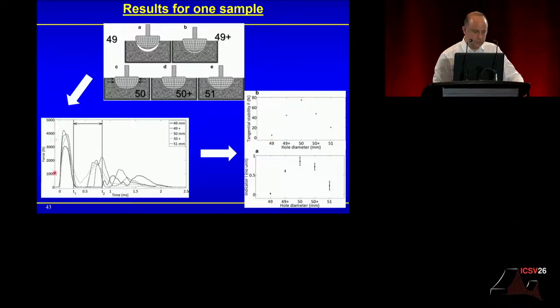Very simple, nothing related to acoustics. But what is related to acoustics is the signal that you see here. That's the signal you get when you impact the hammer when the surgeon decided that it's stable. You have a first peak, and then you have a secondary peak after that. These are reproducible measurements. We hit not too hard in order not to modify the implant, and we get pretty much a good agreement. What we get here is that the first peak is pretty much related to the energy of impaction. Not really a lot of information here, but the information is in the secondary peak.